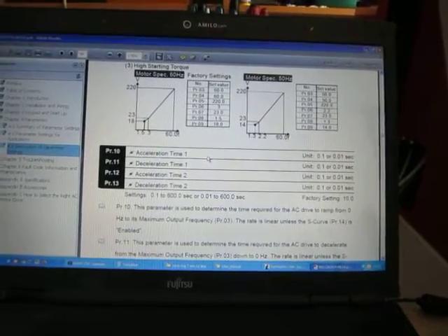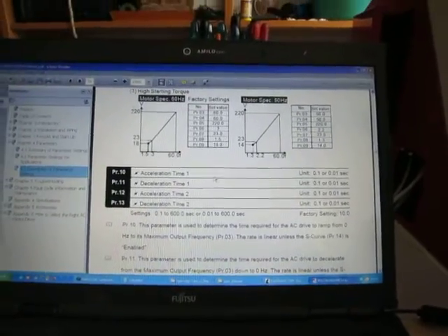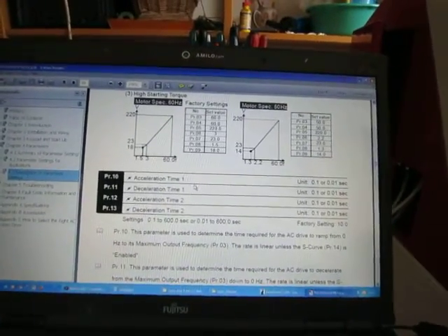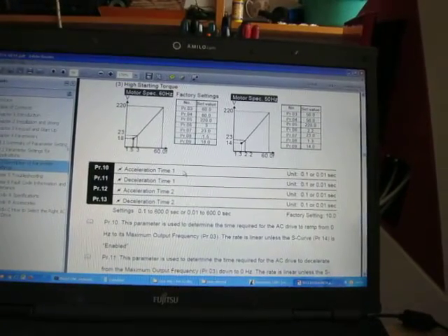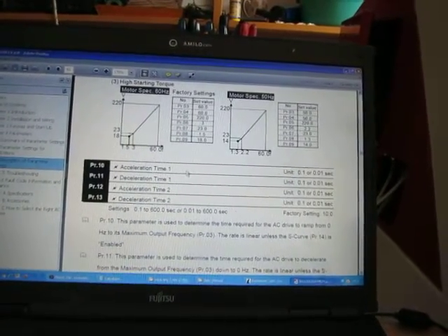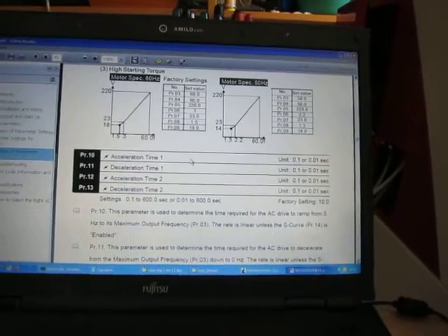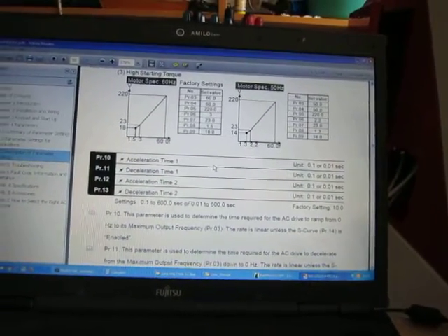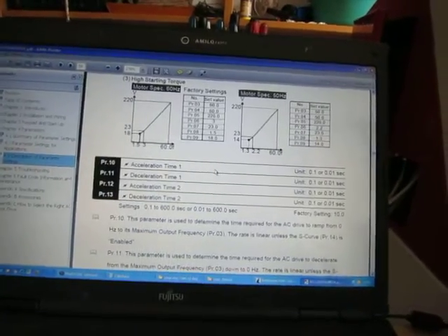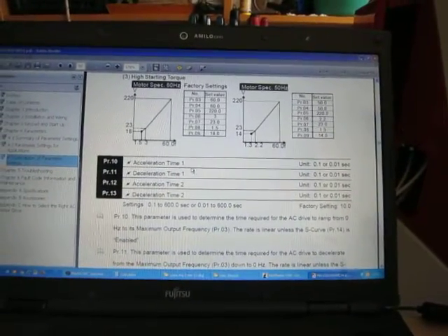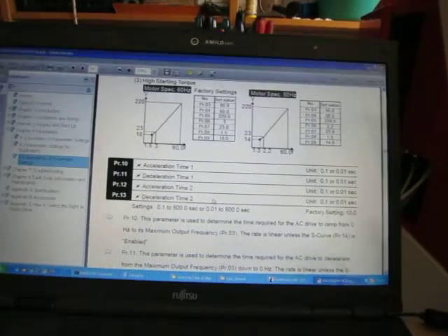I don't know why. So I went to check what will happen if I, for example, change acceleration time from 1.8 seconds to 5 seconds. And I was surprised. It seems like the motor accelerates much faster than when I had 1.8 seconds.